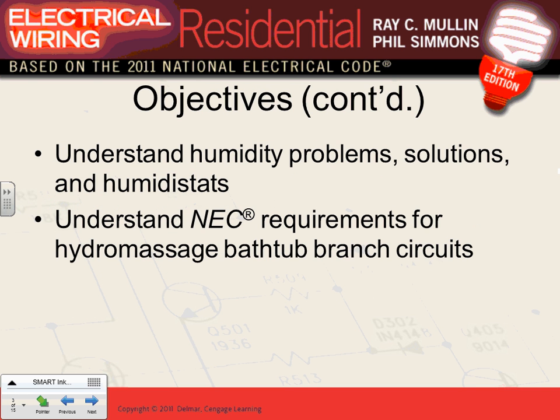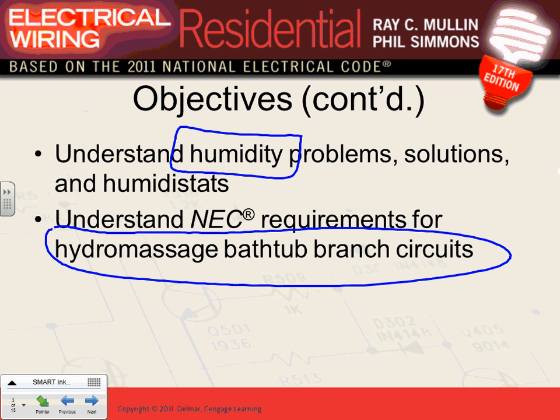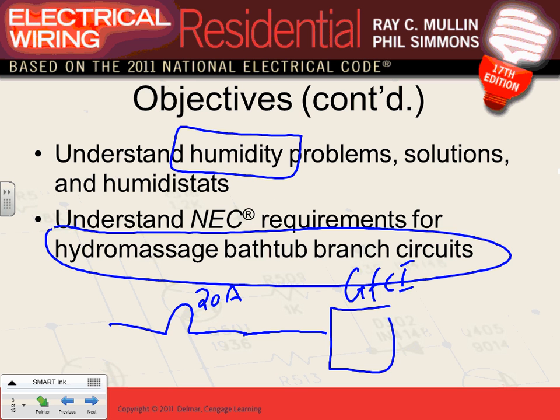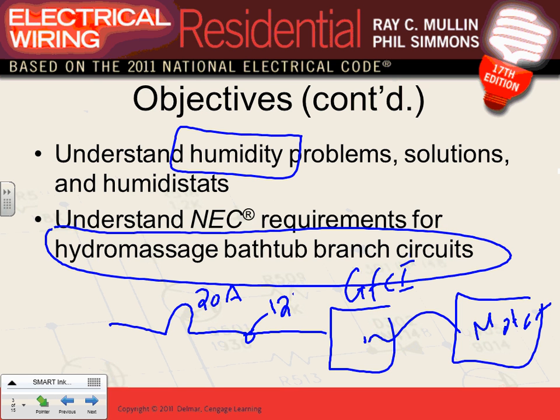Humidity problems. That's why we have a lot of these exhaust fans, guys, the humidity stats and so forth. You put in a humidity stat, so if your humidity goes above a certain value, the humidity stat starts the fan and you reduce your humidity. Branch circuit for the hydromassage bathtub. This is very easy. Here's how we do that one. You take a 20 amp circuit and you bring it into a GFCI receptacle. And here's your motor for the hydromassage bathtub, and you plug it into that GFCI receptacle. Done deal. So the plug itself for the hydromassage bathtub is going to be what? The disconnect. The overcurrent device is already 20 amp by code. This conductor is typically 12-2. And done.